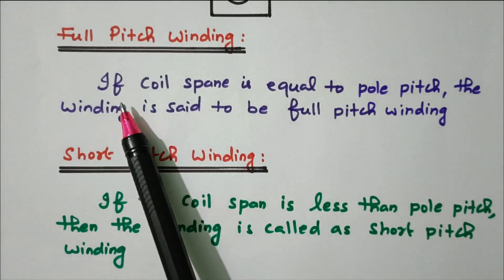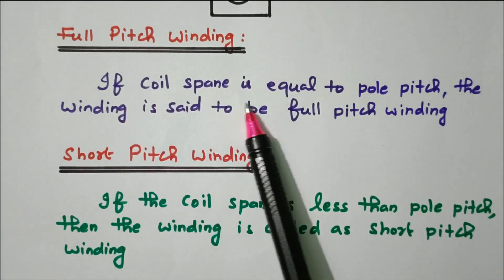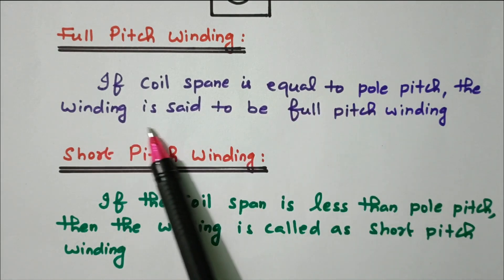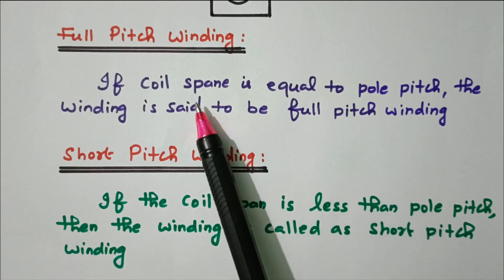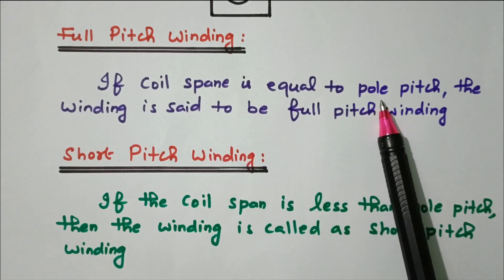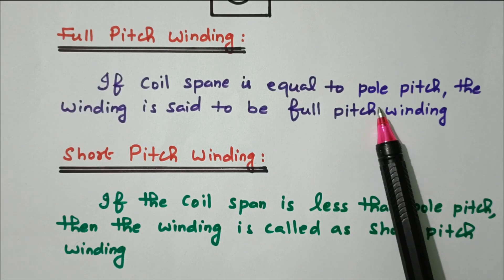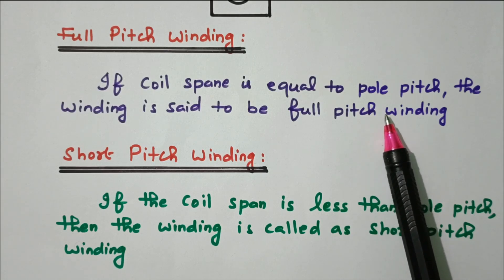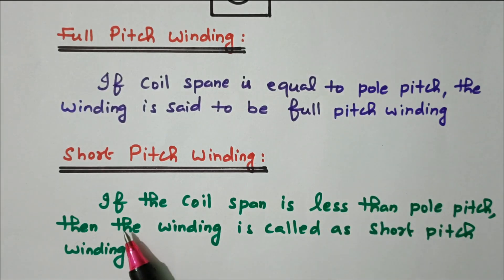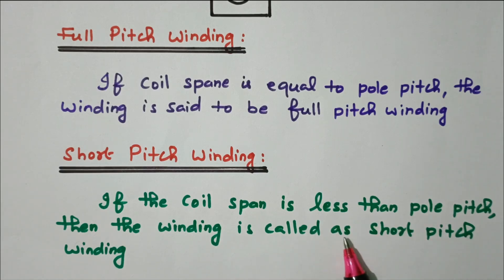If the coil span is equal to the pole pitch, the winding is said to be full pitch winding. Coil span is the number of armature conductors between the two sides of the coil; pole pitch is slots per pole. If both are equal, it is called full pitch winding. If the coil span is less than the pole pitch, then the winding is called short pitch winding.